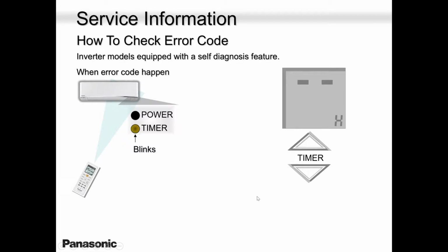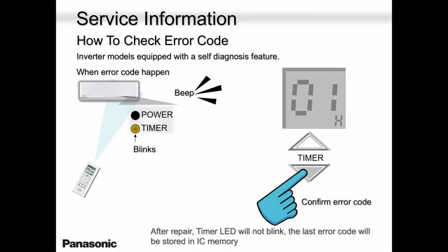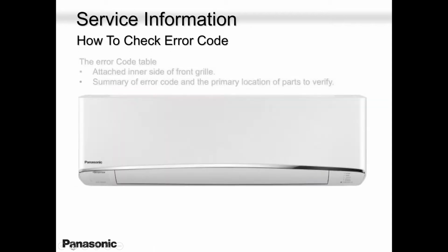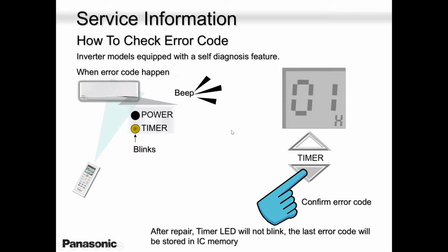And we have 2 letters only on our error codes. The 2 letters are H as in Henry and F as in Frank. So you will scroll through all the Hs first, and then you will scroll to all the Fs. And depending on what error code you have, you can find out what the problem is. And we have an app. So when you get to the error code, let's say H11, it will beep and you will see H11 here. And the indoor unit will beep. So just to be sure that the error code is H11 or H99 and not F11 or F whatever, go all the way through all the error codes and come back again to where it was beeping.